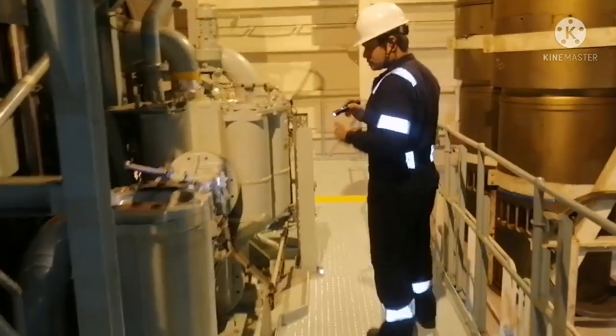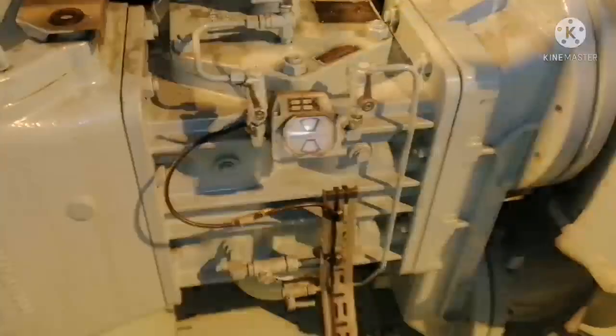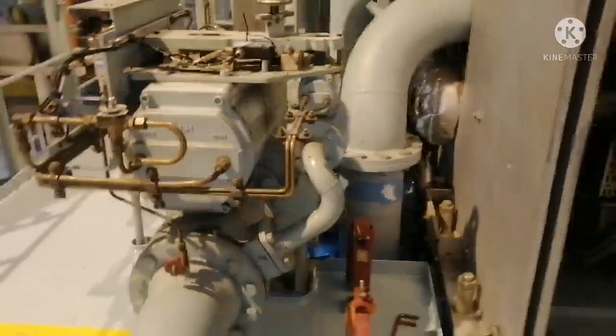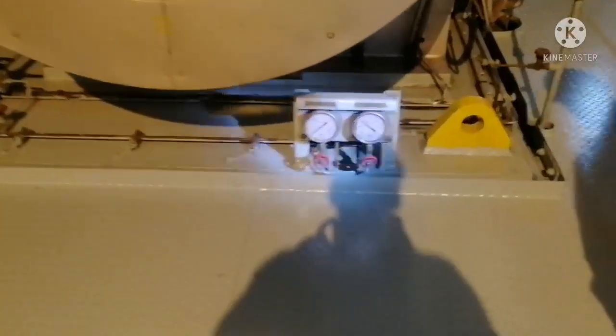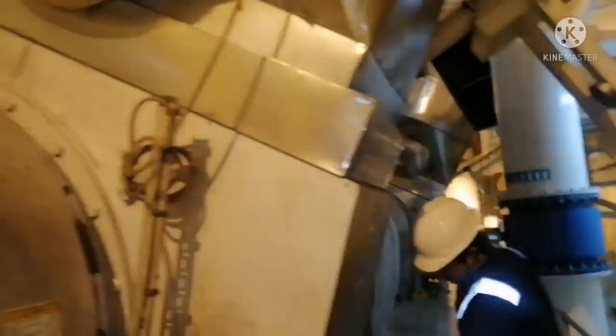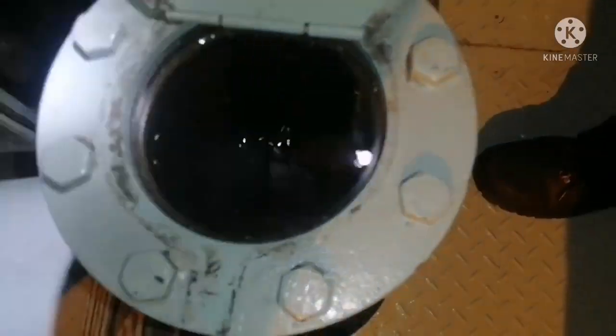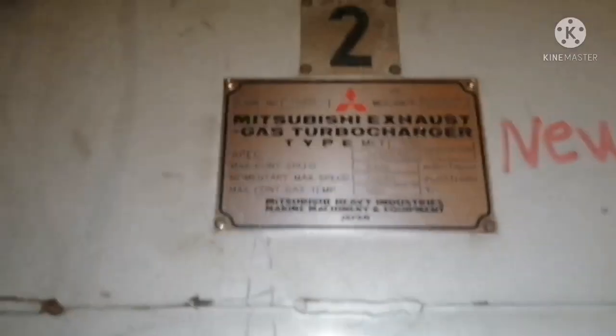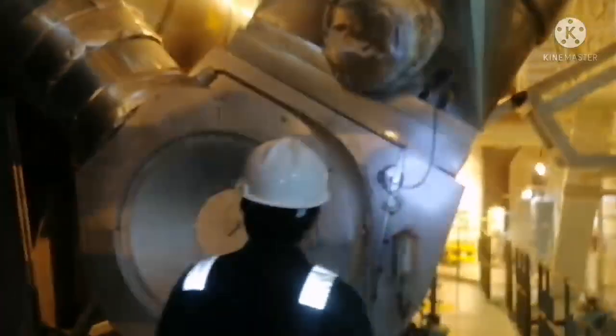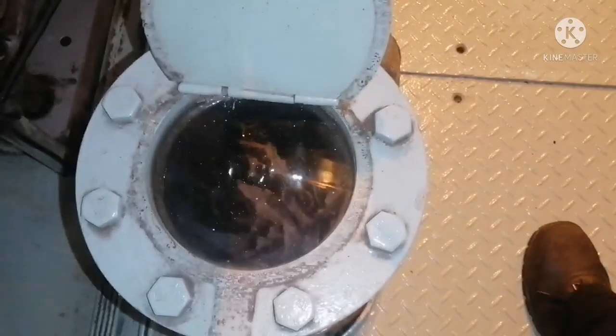So the main thing is you have to ensure there are no leakages, and this is your lube oil auto filter. Ensure that there is no differential pressure high alarm. This is your starting air valve, main starting air valve line. Ensure there is no vibration on that. And this is your turbocharger. So for the turbocharger, all you need to check is the lube oil flow in the turbocharger, and you have to check the lube oil temperature and exhaust gas inlet and outlet temperature. Exhaust gas inlet and outlet temperature you can even see in the MOP, like in the computer which is kept in the engine control room. And this engine has two turbochargers. So for both turbochargers, you have to check the lube oil flow, and the temperature of lube oil and everything.